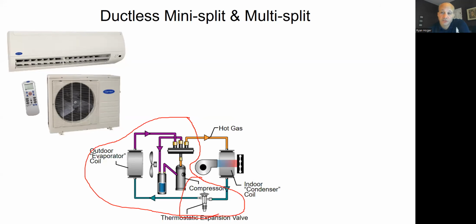So what does that mean for you? From an operational standpoint, it doesn't mean anything for you. It works exactly the same way. The fundamentals are the same. The servicing is the same. Installation-wise, it is a little bit different. The two refrigerant lines connecting these guys, because this device is out here, both lines have to be insulated on these ductless mini splits. Not every single manufacturer, but nearly every manufacturer does it that way.